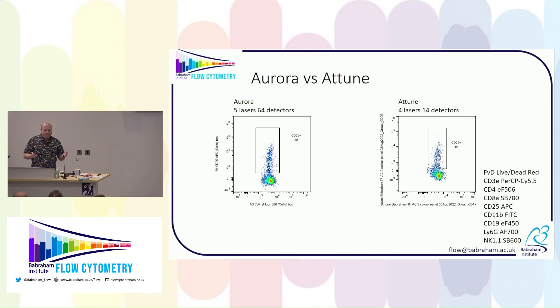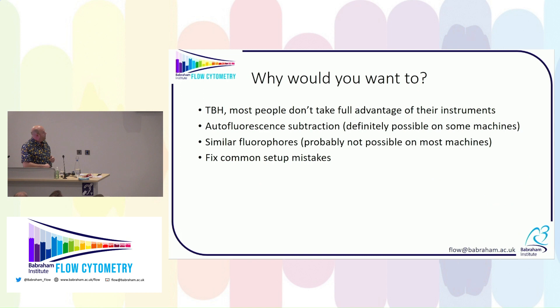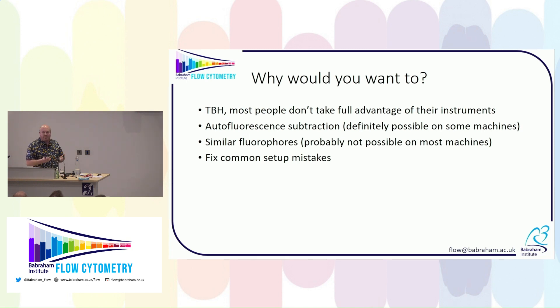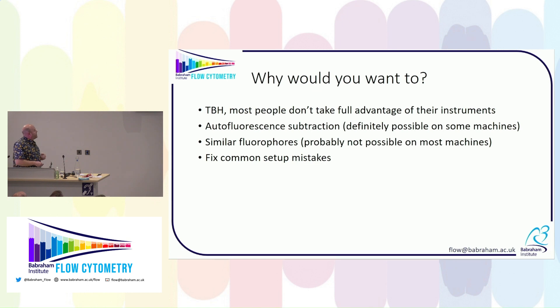The whole point of unmixing is you have more detectors than parameters — it's an over-determined system. Any system that has fewer fluorophores than detectors is over-determined, so you can do the unmixing. The reason you'd want to do it is that most people, even on the Auroras, really don't utilise the entire capability of the machine. And because of that, you can do interesting computational tasks such as autofluorescence subtraction, unmixing similar fluorophores, and fixing common setup mistakes.